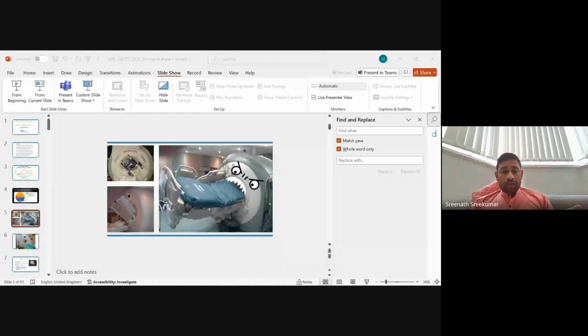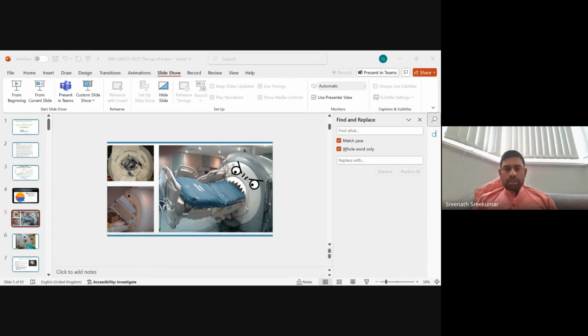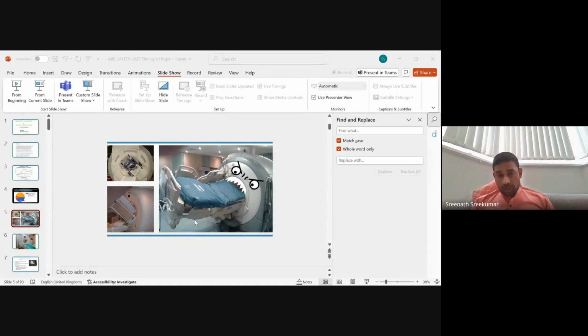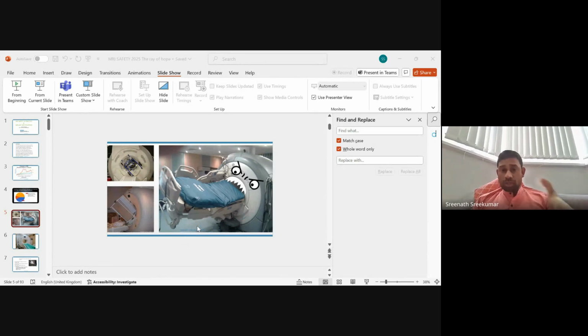If we have to cut off the electrical power inside the magnet room, we have to press the emergency off. If you have to cut all the systems inside or outside or anywhere within the MRI premises, you have to use the emergency stop. We can use these in any other situations. These two switches have nothing to do with the quenching button or quenching system. They only turn off other associated power supplies to the machine.